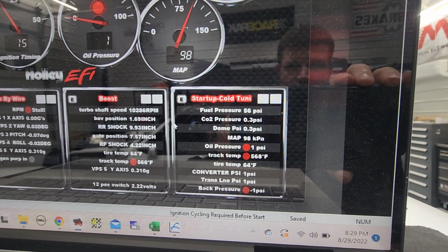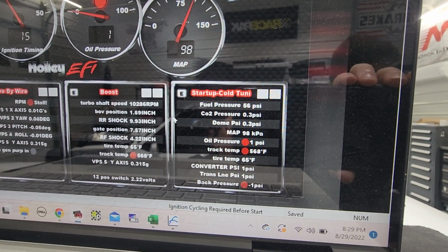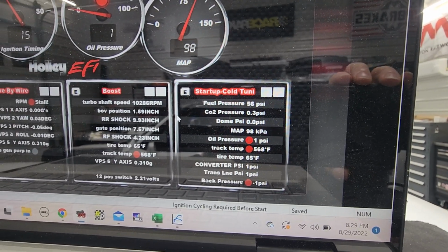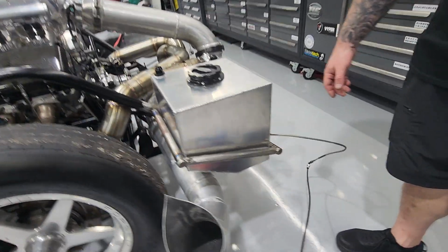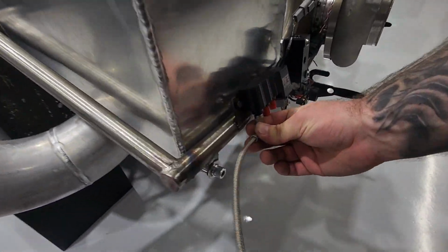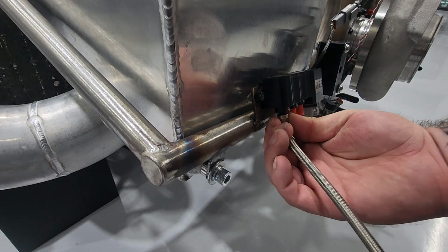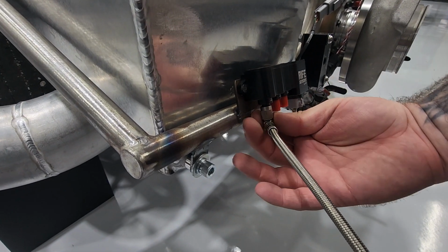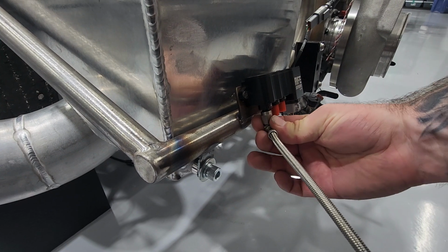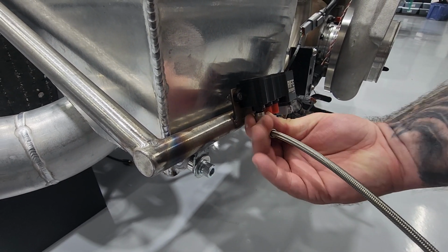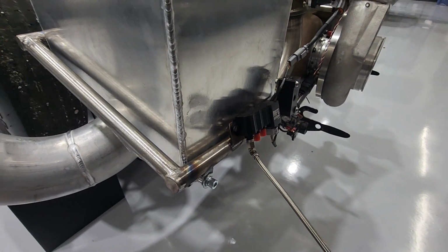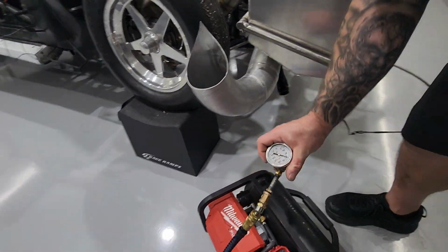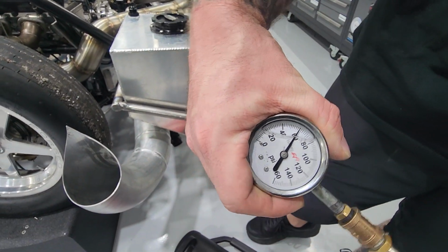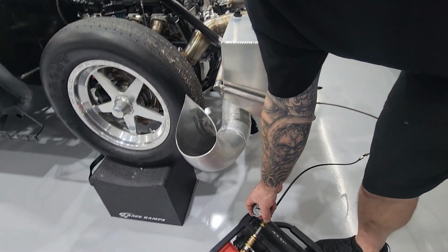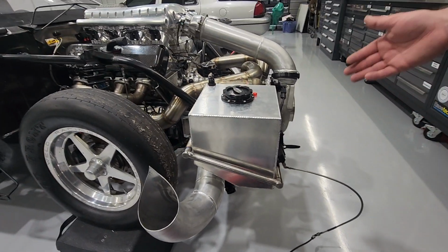But is it leaking from here, from this gauge to where it's hooked up? Probably, and the reason I say that is because it's hand tight. So I don't look for an exact number here, but this thing's hand tight, so yes, it's leaking - you can hear it, it's pissing a little bit. So my gauge reading 60 here, and us only having 55 there, is not a big surprise. But either way, we know that it is wired correctly.